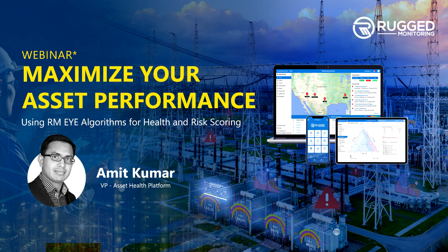For example, we identified faults in two transformers, or at least the health of those two transformers had gone down. When they did an independent analysis with a third party testing company just to verify, they found similar results. This proves that the health index calculations and fault diagnosis calculations we provide are accurate enough, and it's helping them improve their current practices.